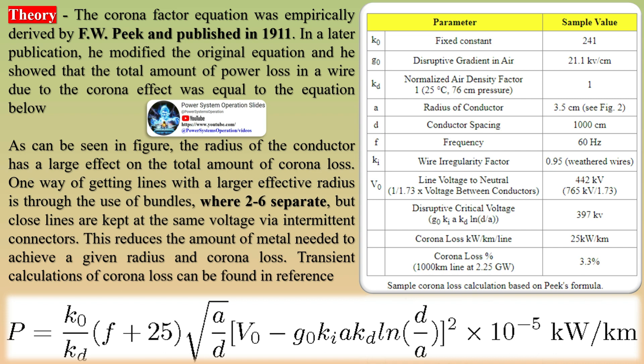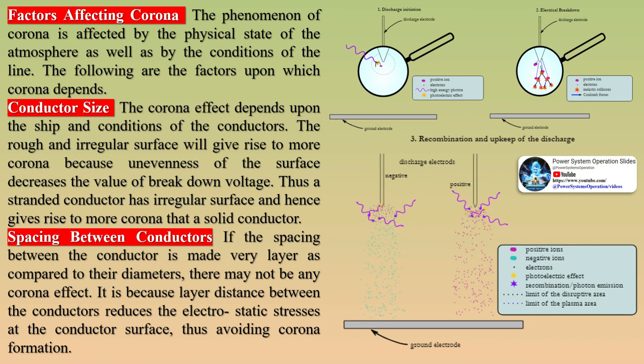Corona discharge power losses are also highly dependent on weather and temperature. The corona factor equation was empirically derived by F.W. Peek and published in 1911. In a later publication, he modified the original equation and showed that the total amount of power loss in a wire due to the corona effect was equal to the equation. The radius of the conductor has a large effect on the total amount of corona loss. One way of achieving lines with a larger effective radius is through the use of bundles, where two to six separate but close lines are kept at the same voltage via intermittent connectors, reducing the metal needed to achieve a given radius and corona loss.